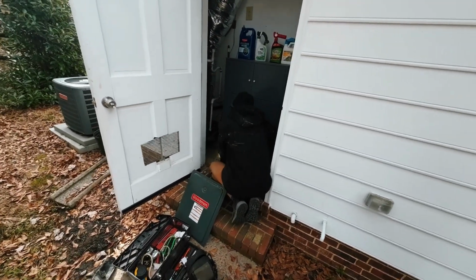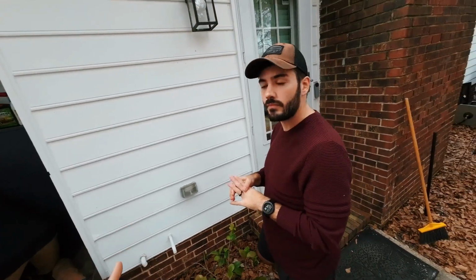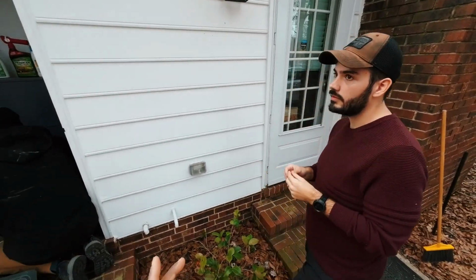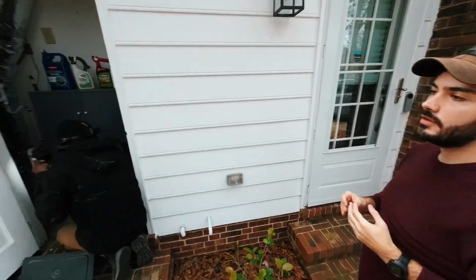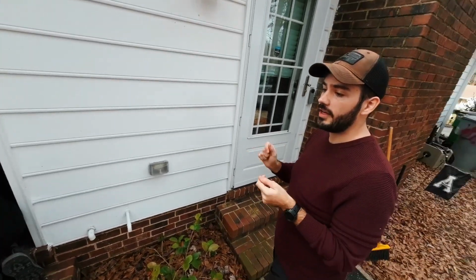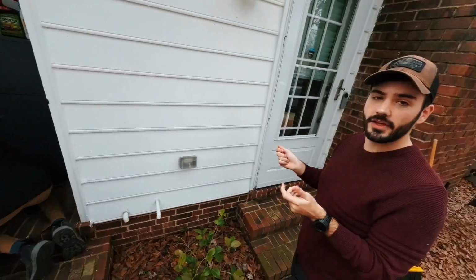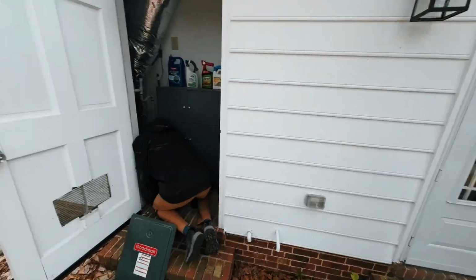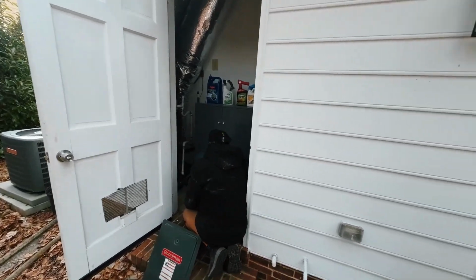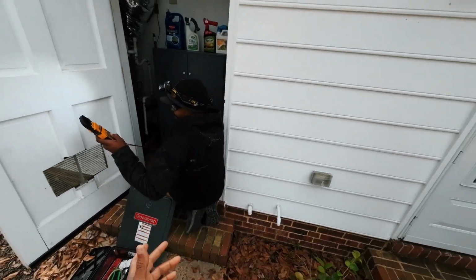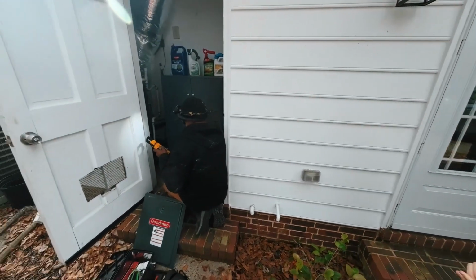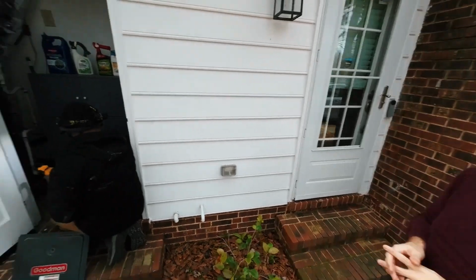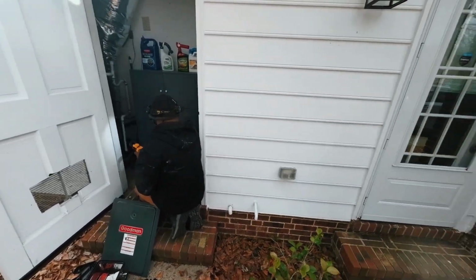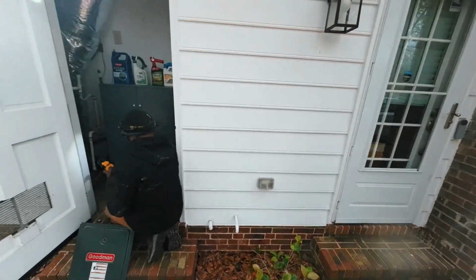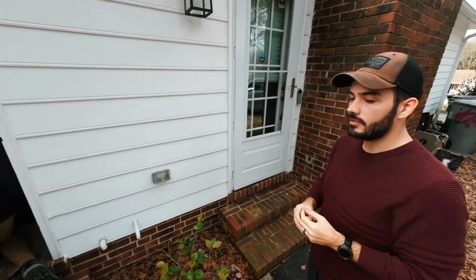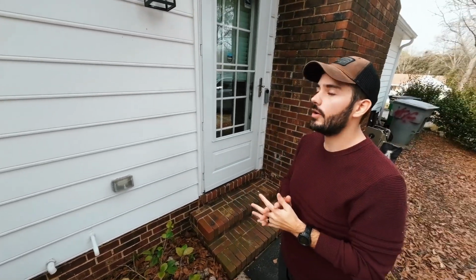Essentially, I think they even do 4-inch inserts for the indoor unit mounted on your wall as well. So I'll look into getting at least a 2-inch for that. I think the 2 will do just fine. But you also have to consider this is heating mode, so cooling mode will have a lot more airflow. The fan speed ramps up in cooling mode, so the static pressure will be higher - you're probably going to be running about 0.8 in cooling mode, more than likely.